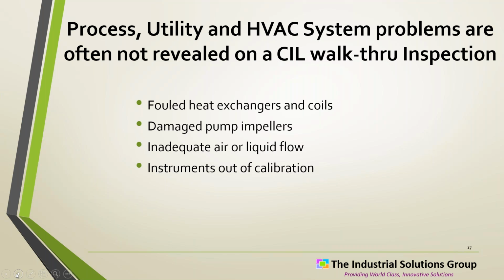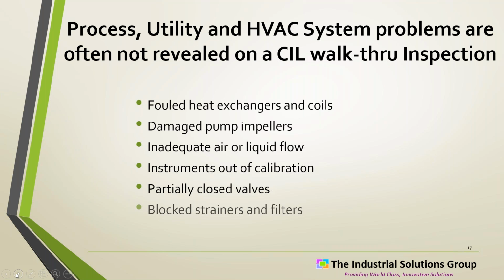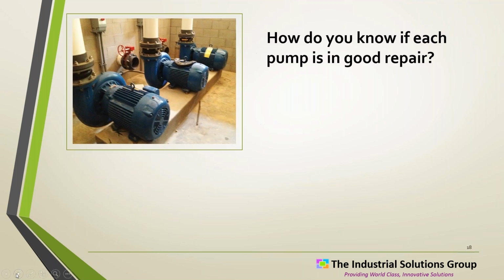I see a lot of pressure and temperature gauges, and it's not uncommon. I'll say, boy, that looks like a high temperature, and the answer will come back, well, yeah, but we don't trust that. That's out of calibration. And sure enough, there's an electronic instrument they trust more, and there's a 4 or 5 degree difference between the two of them. So which one to believe? Very common problem. You have instruments, you just don't believe them. You can't believe them. You can have partially closed valves, valve seats that leak, and other things where you think you got something closed. It's not. Things that get blocked, strainers and filters, just on and on and on. And all of these are invisible on a walkthrough. You just can't see it.